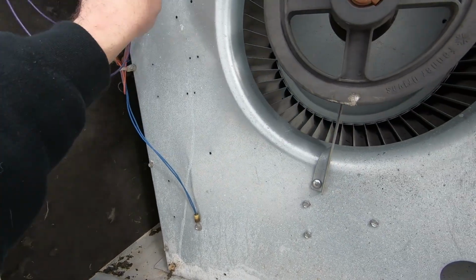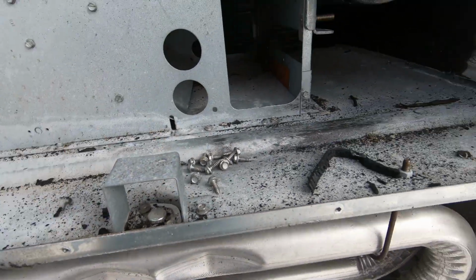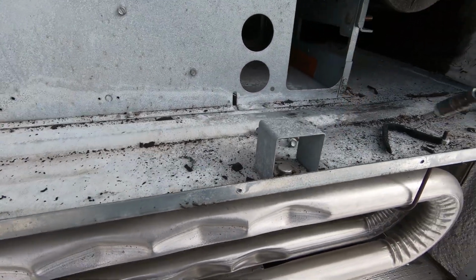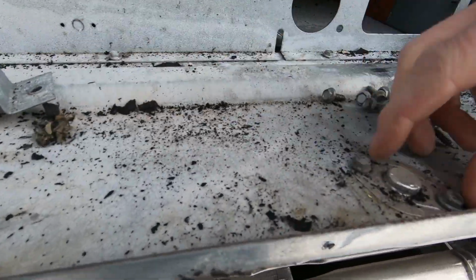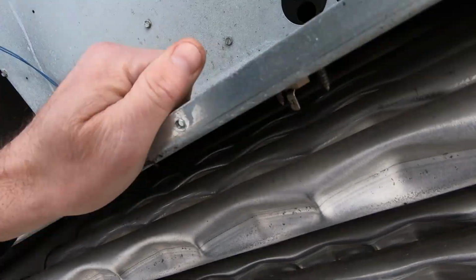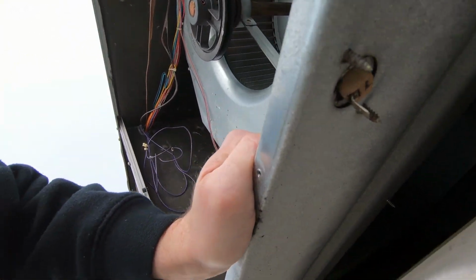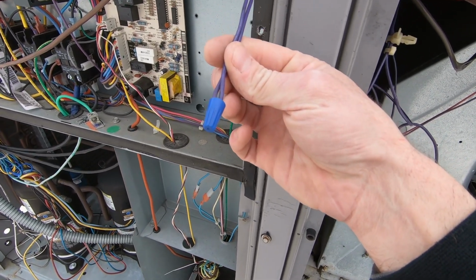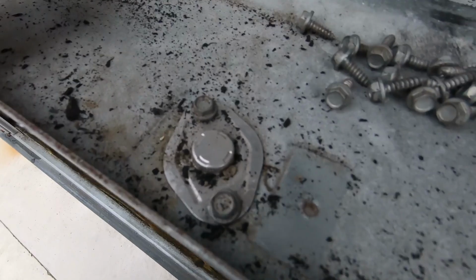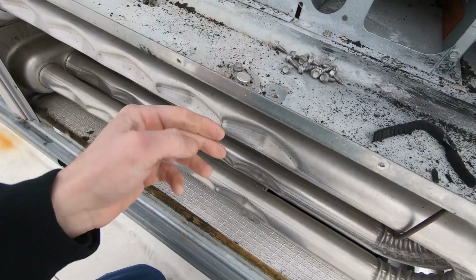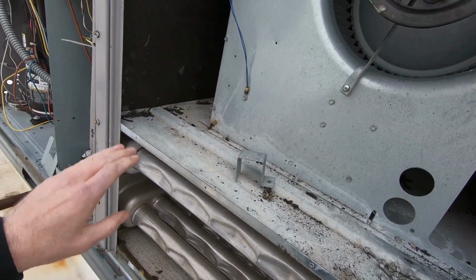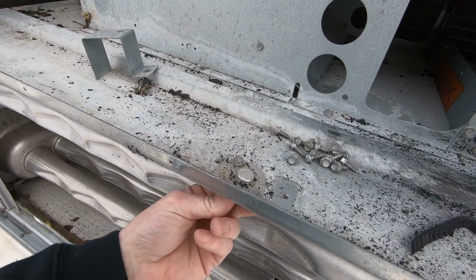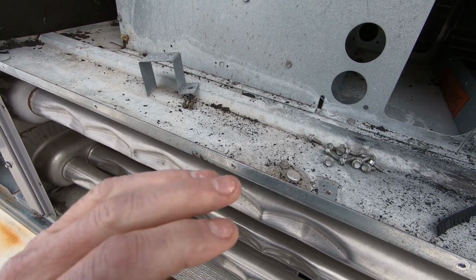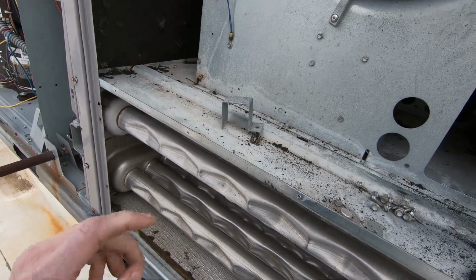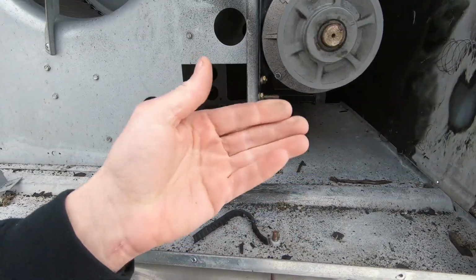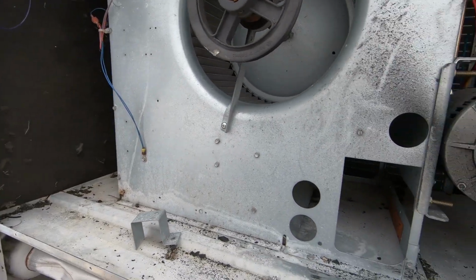Well, the heat exchanger does not appear to be cracked, but let me tell you, I've never seen this before. This limit switch is in upside down. Oh, it's broke too. Right here's our limit wires jumped out. Have you guys ever seen, I mean, who would mount a limit like that? It's supposed to sense down here. So somebody bypassed the limit because it was broke and flipped it upside down for some reason. It never tripped the limit. So this thing just fired and fired and fired, and melted the wires.